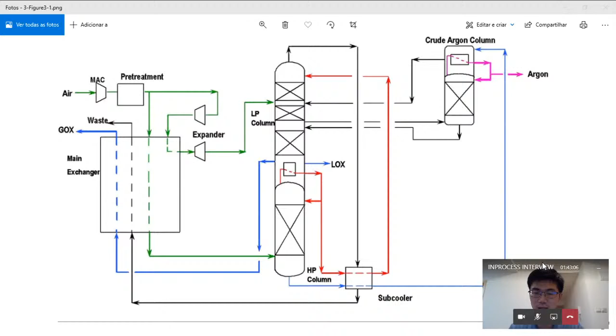It's different when you are on site. If you are on site, the focus shifts to plant commissioning, adjustment, or optimization, like finding that a temperature has changed abnormally. So first you need to check whether the temperature element is installed correctly on site, then compare with the design data, and maybe do further calculations to decide if it's okay or not. You need to use your design experience to tell what the gap is, because sometimes a temperature reading looks okay but actually isn't.